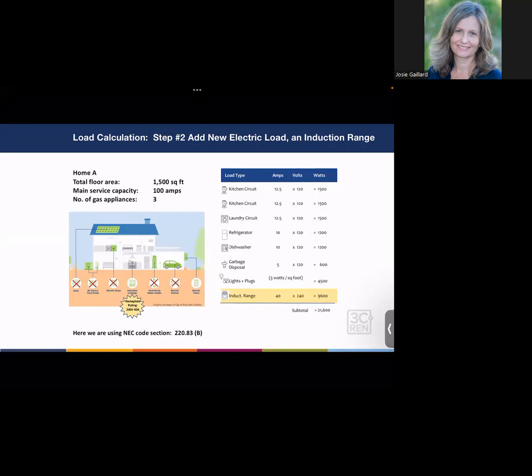The code assumes every home has 2 kitchen circuits, listed at the top, each at 12.5 amps and 120 volts. That's prescribed by the code. Similarly, the code requires every home to have 1 laundry circuit, again 12.5 amps and 120 volts.